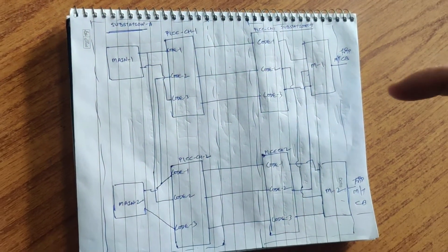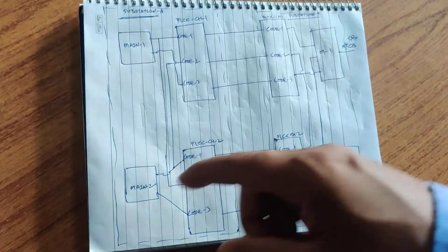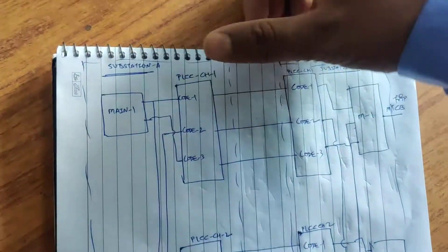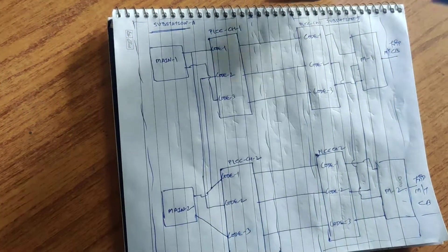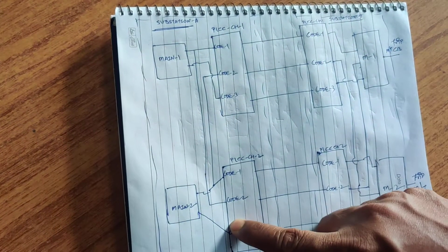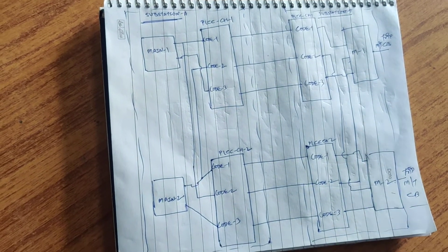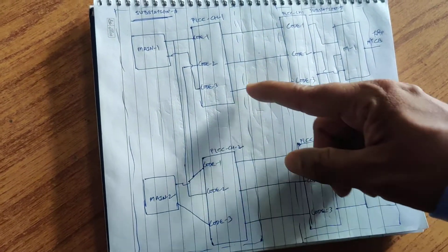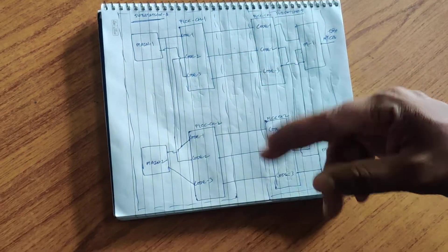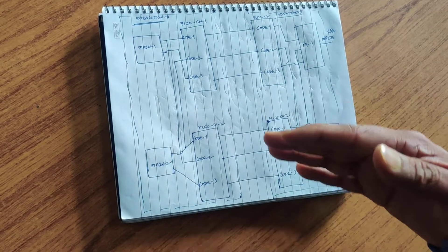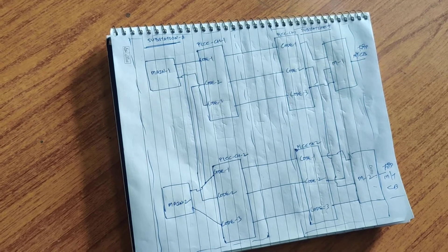We use both code one and code two for the permissive scheme. For example, in an under-reaching scheme, main one relay will send the carrier after zone one picks up. Main one relay has two outputs: one connected to channel one code one, and the second connected to channel two code two. Similarly, main two relay also has two outputs: one connected to channel two code one, and another to channel one code two. Code three is for direct tripping only, so a single output from both main one and main two relay is used for code three.